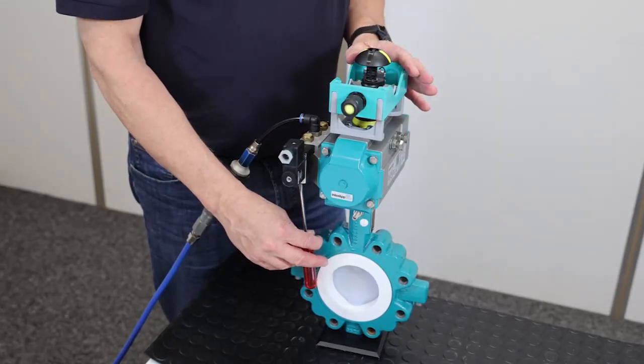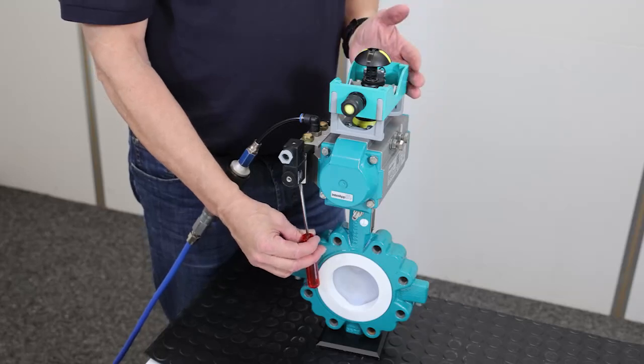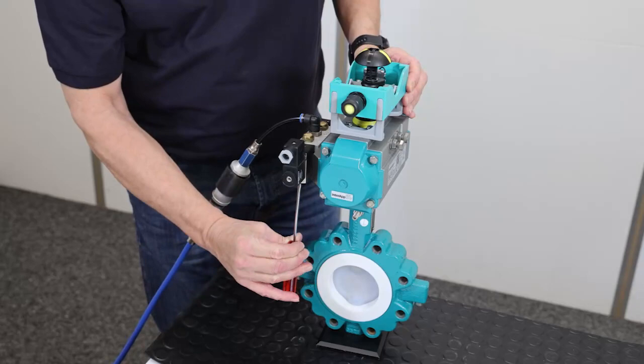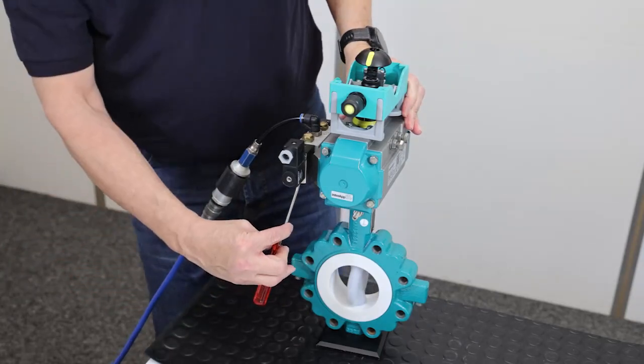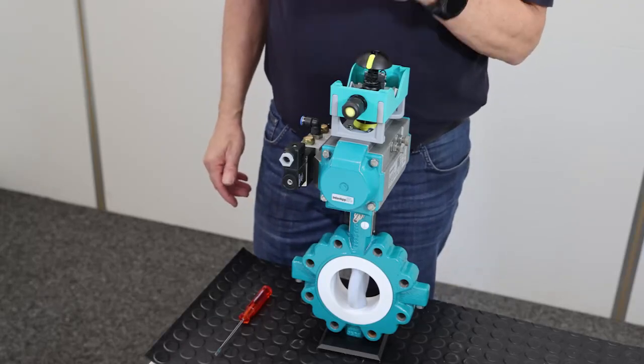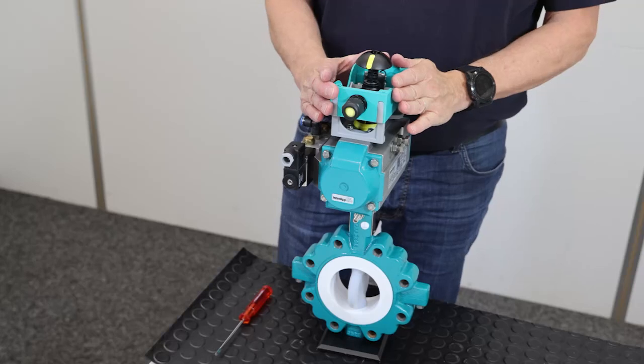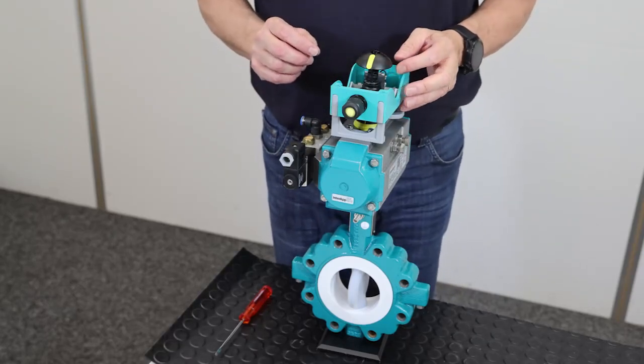Now we will control the open position. For this, we need to operate the actuator using compressed air. The position indicator shows the position of the disc, so the valve is fully open. Now we can check the open position.